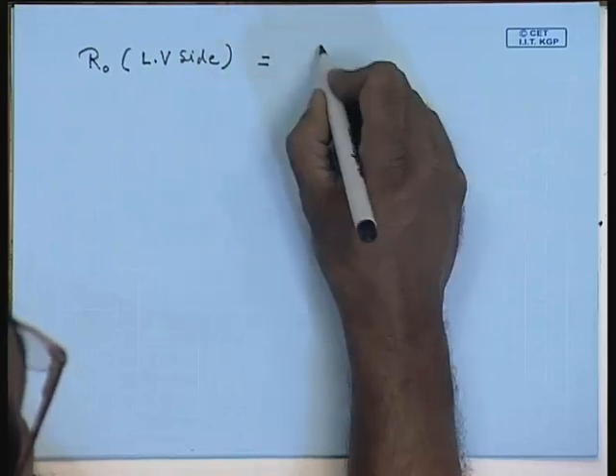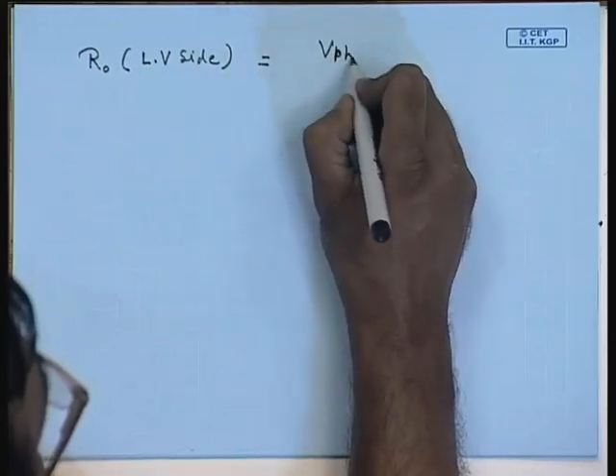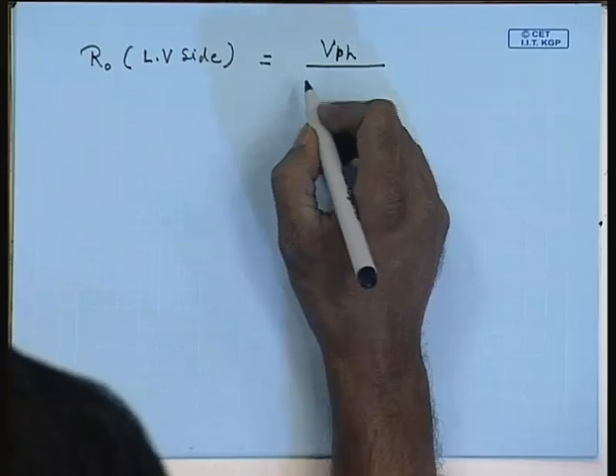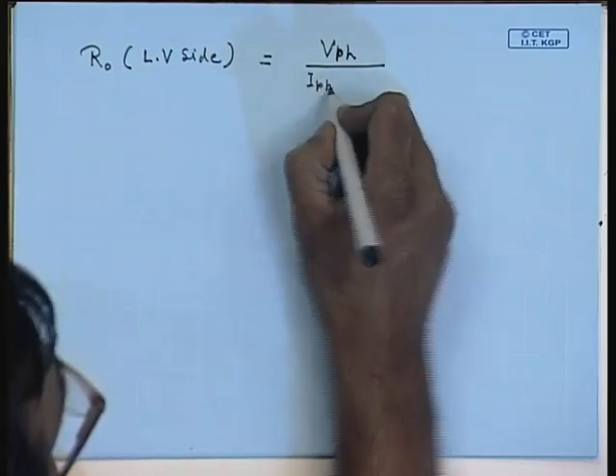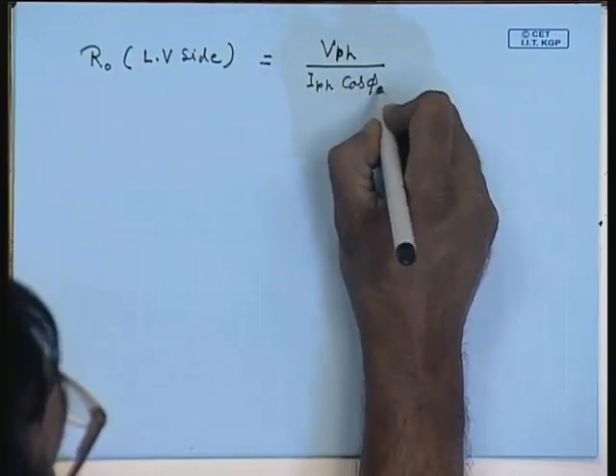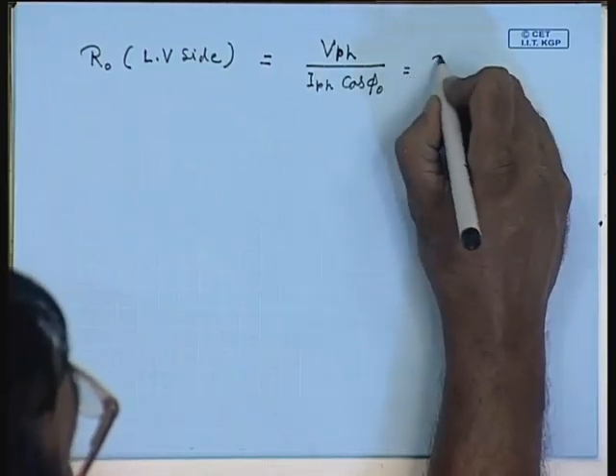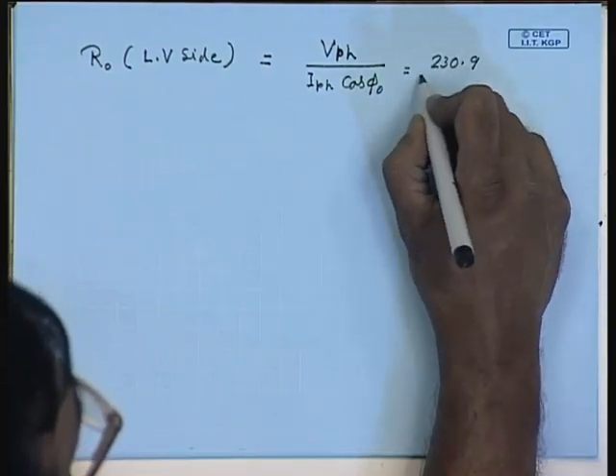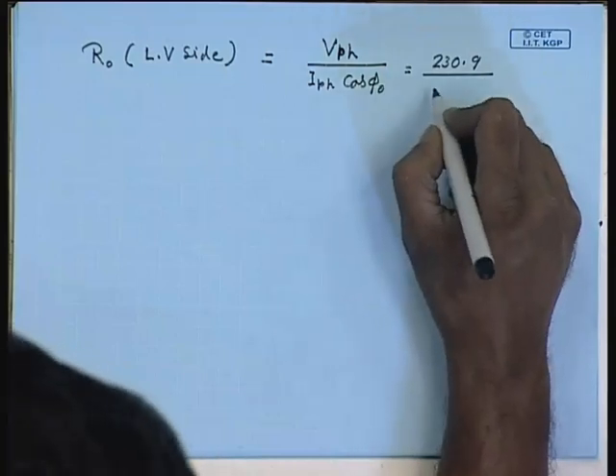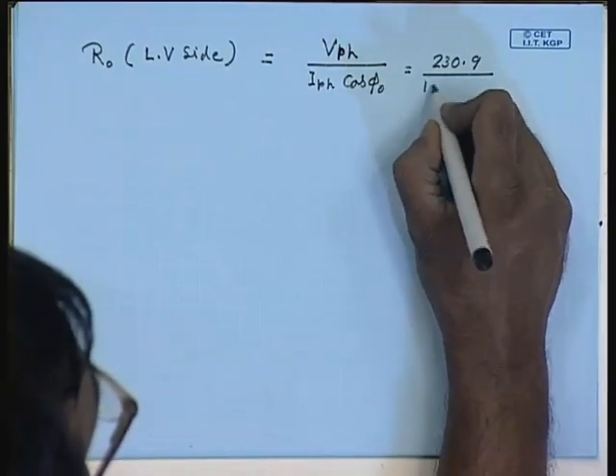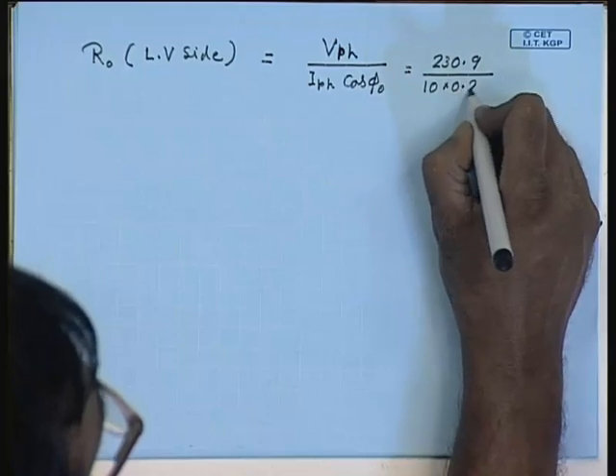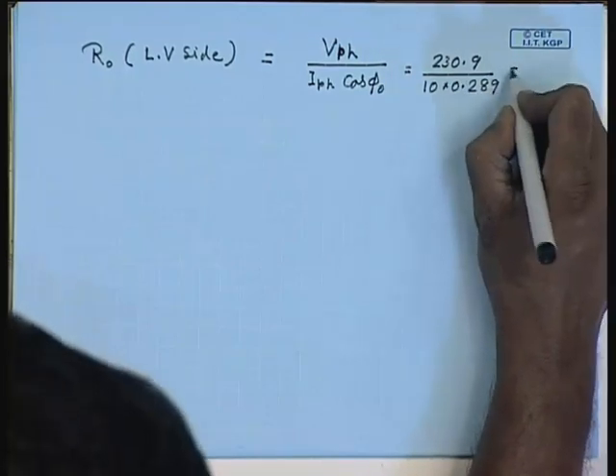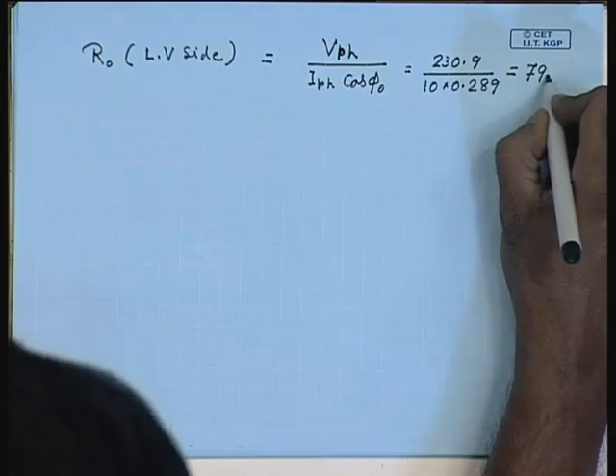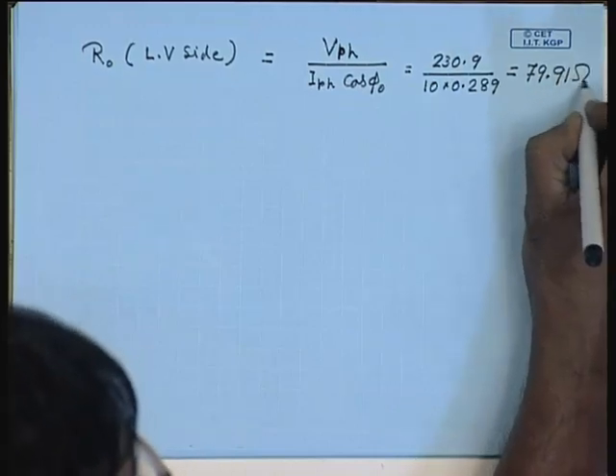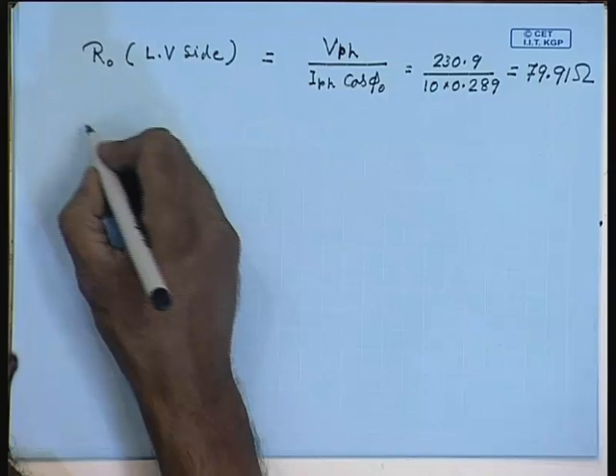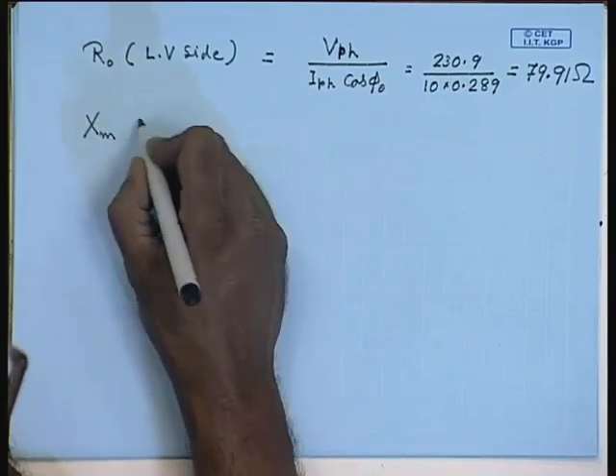This is found as V phase divided by I phase cos phi 0, that is 230.9 divided by 10 into 0.289, this comes to 79.91 ohm.